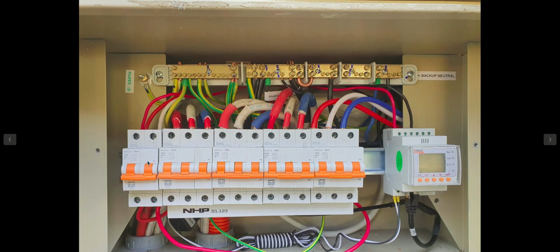So here's the main switchboard. There's the, I like 2-pole. I don't like turning off an inverter and then you could have the backup supply still going, or you could have grid. You want to isolate. That to me is isolating the grid side and the backup side all in one. I like the 2-pole. Gee, I've got a lot of shit here.